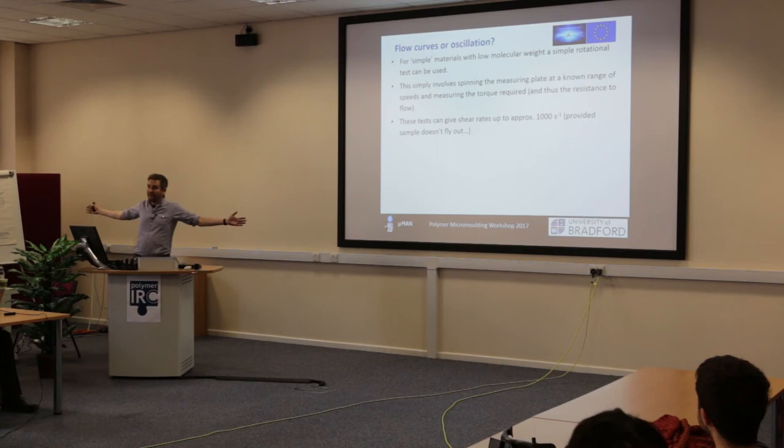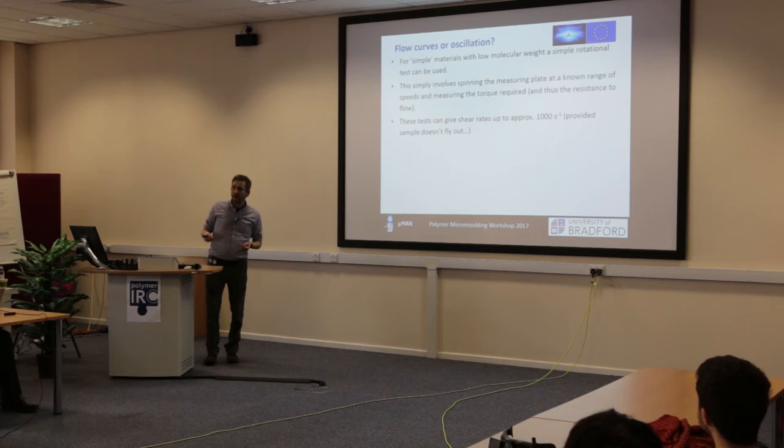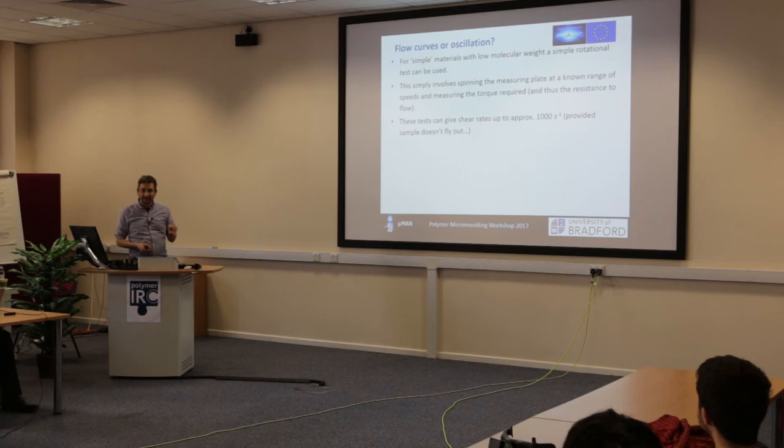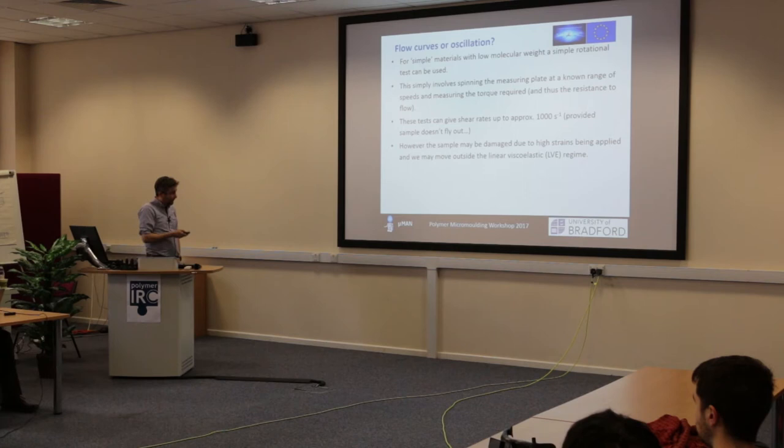And there's lots of papers published whereby they show this high shear rate behavior where you get this massive drop in viscosity, which actually means they've just lost all their sample. And it's flown all over the room. They haven't noticed, okay? Loads of papers about it, okay? If you go beyond that, you're knackered, all right?